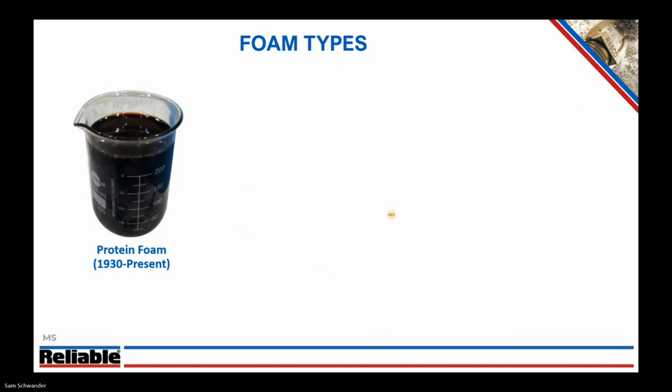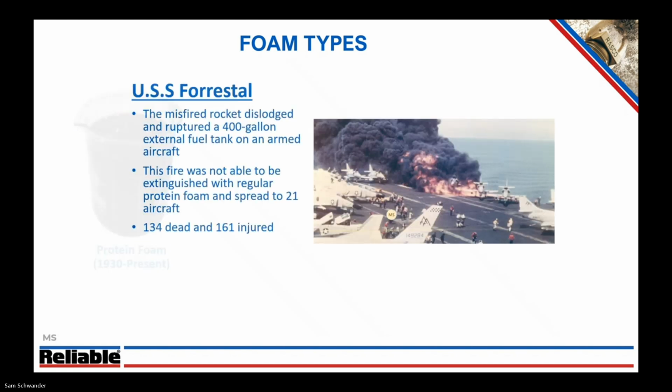a firefighting foam concentrate. You chop up the pieces a little too far, you get really nice foam, but not very good performance. You don't chop up the pieces far enough, you get good fire performance, but you get a lot of sedimentation. So it's really trying to find a happy medium there for that hydrolyzation process. So not perfect, but it does work to put out a lot of fires.